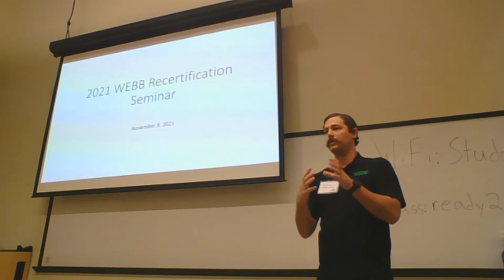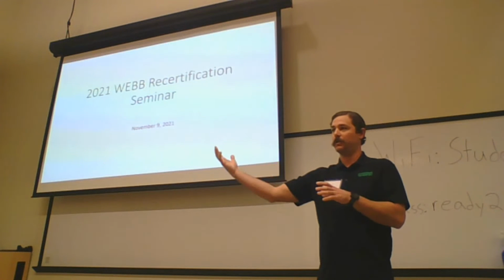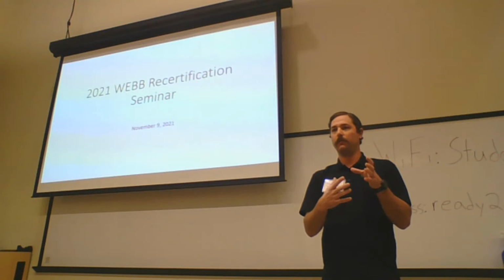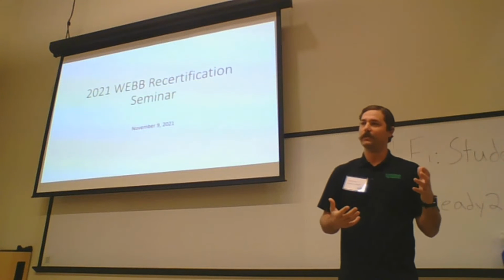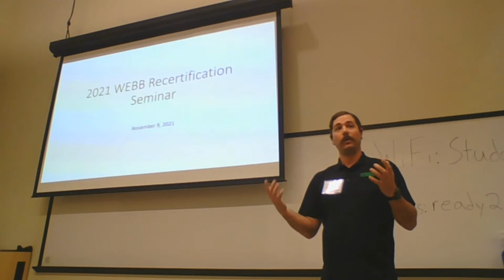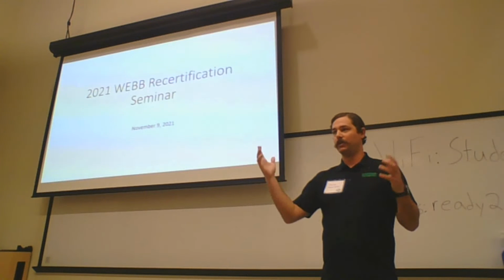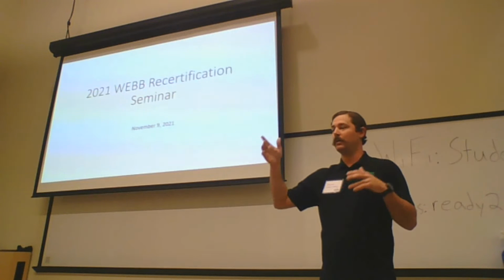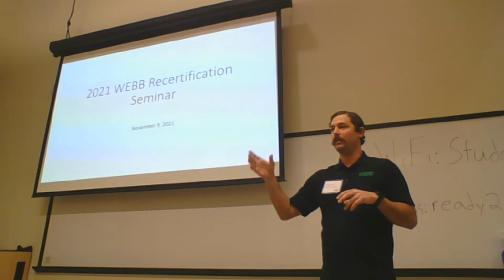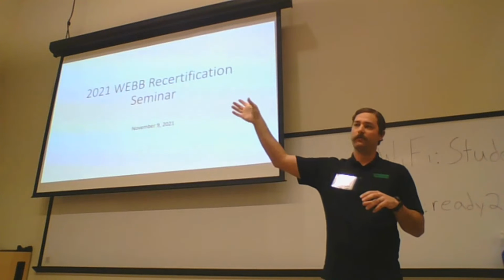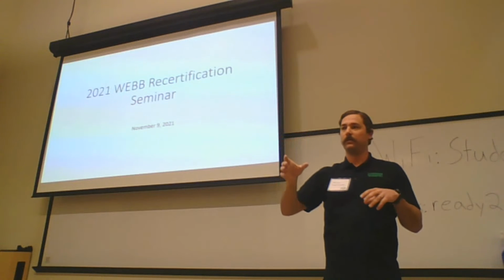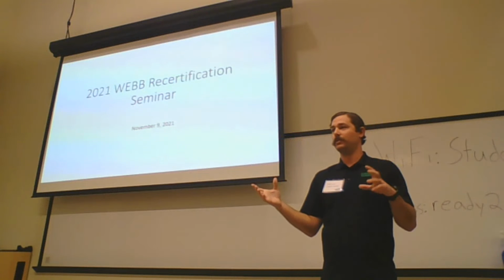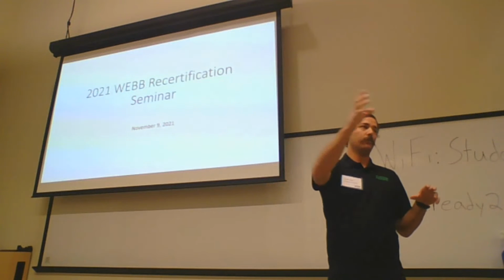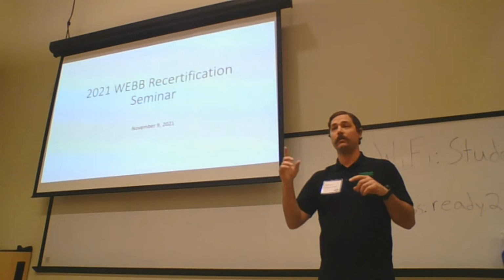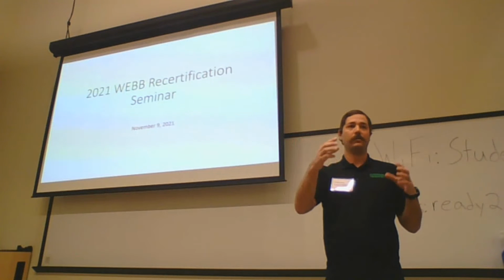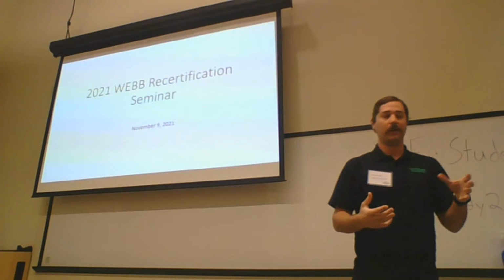That's just one example, with your hood reporting into one device. But as we open things up, if you're doing a pressure study, like door pressure for an entire hallway or stairwell, we can set these sensors in various locations, up to eight different differential pressure sensors around the room. As you make your changes, you can record and see that data change in real time, all on one parent device.